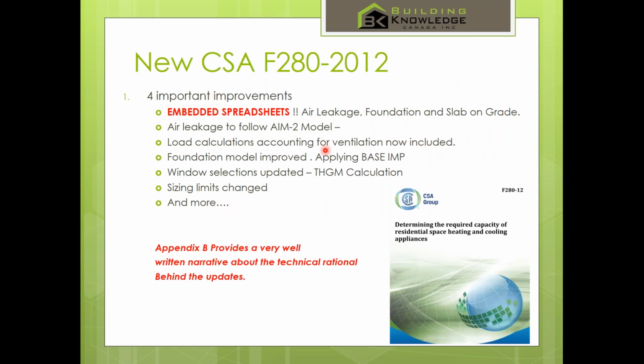The new F280 has embedded spreadsheets, which is important to understand. It's the first time a CSA standard has had that, so you actually have to use these calculation spreadsheets embedded in the standard. And it uses a new calculation for air leakage, which is what HOT2000 has used for years, the Alberta infiltration model. New way to do windows, new way to do foundations, some sizing limits have changed, and so on and so forth. And if you're losing sleep and you can't sleep at night, go to Appendix B and read it. It gives you an idea why things have changed. It's actually a very good narrative that was done by the authors.